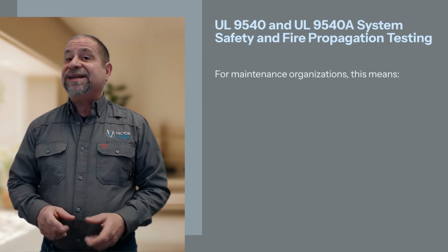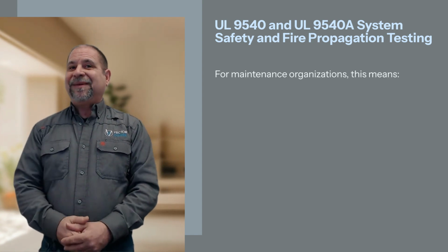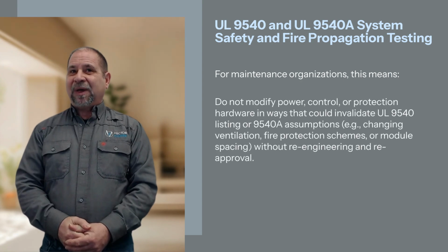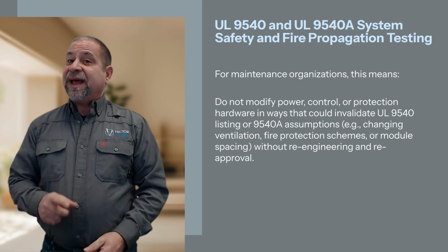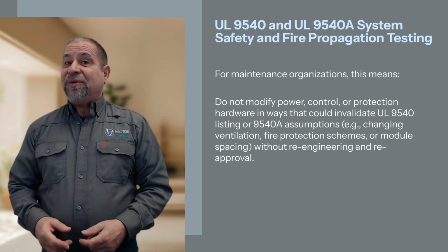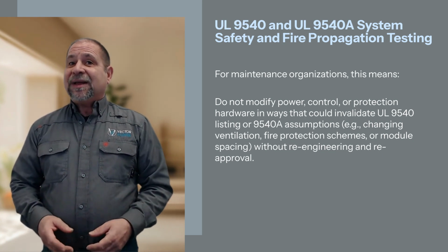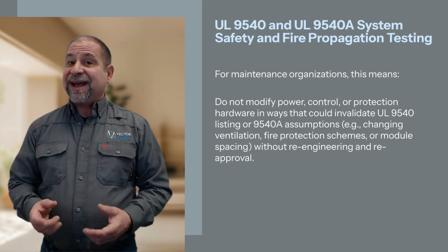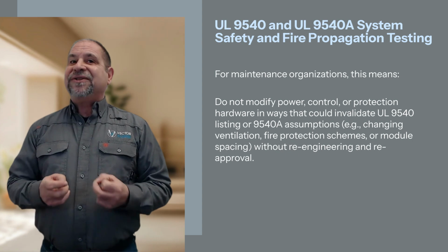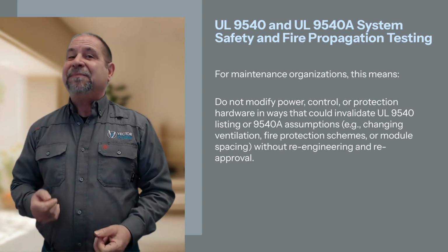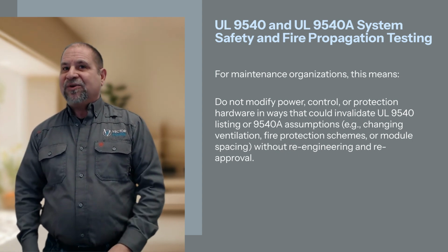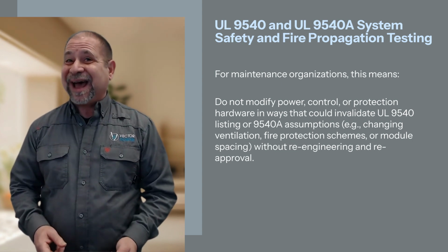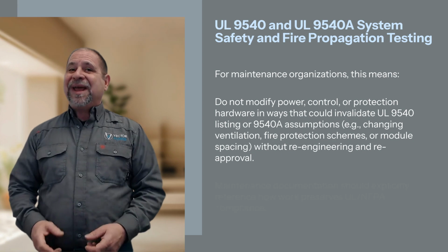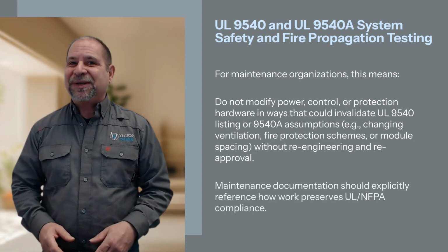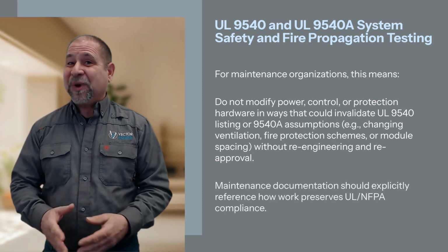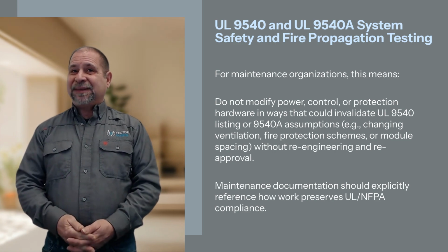For maintenance organizations, this means do not modify power, control, or protection hardware in ways that could invalidate UL 9540 listing or 9540A assumptions, for example, changing ventilation, fire protection schemes, or module spacing without re-engineering and reapproval. And maintenance documentation should explicitly reference how work preserves UL and NFPA compliance.